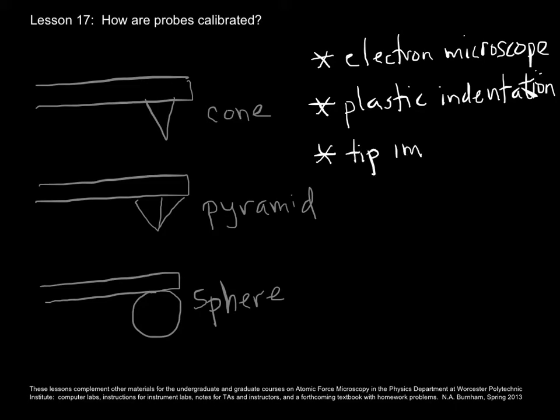You can also go over a sharp feature, a feature that is sharper than the tip on your cantilever. I gave a lesson on that called tip imaging. I believe it was lesson 5. And that sharp feature, it could be a spike. You can buy those delta function gratings, as I call them. You could use a sharp edge, or you could use a hole in the sample. So the presumption is you know the shape of that sharp feature, and that sharp feature is much smaller than your tip. And finally, there's something called tip reconstruction.